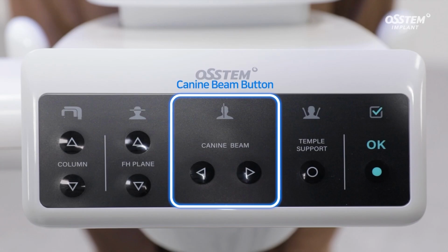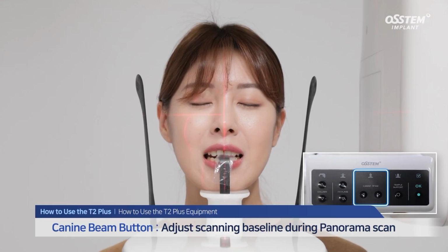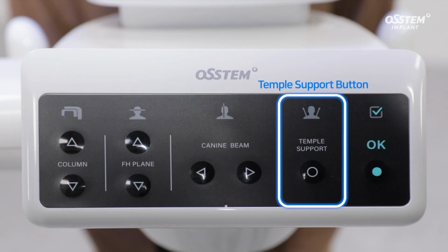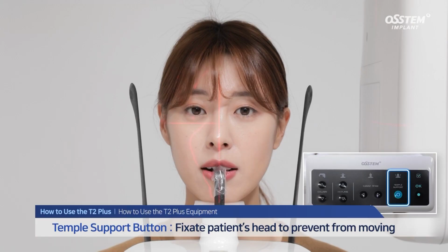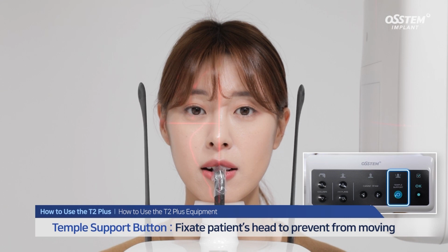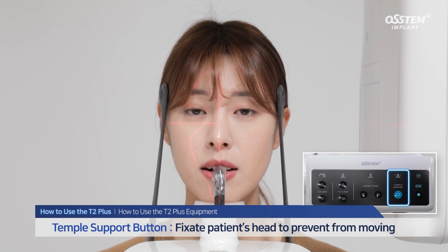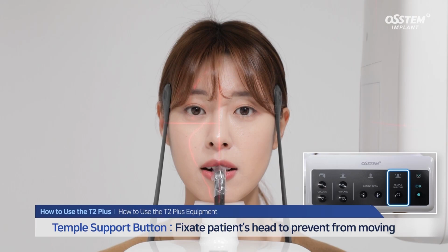Canine beam button. The beam button adjusts the position of the canines, which is the starting point of the panorama scan. Press the button to place it on the canine. Temple support button. This fixates the patient's head to prevent it from moving during the scan. Pressing this button during the panorama or CT scan enables fixation, and pressing it once more releases it.